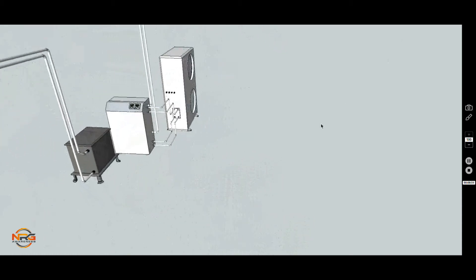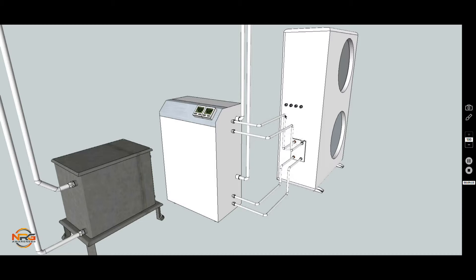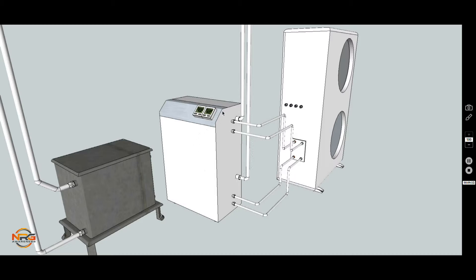If we look at what's happening with the heat pump, we have two parts. We have the outside, which is made up of two different heat collectors or heat pump apparatus, with refrigerant circuits coming from both of those, the top one and the lower one. This refrigerant would be pushed through the compressor, would increase the temperature of the refrigerant gas accordingly, and that high temperature refrigerant gas would be put through a plate exchanger within the unit. Likewise with the bottom one if it's operating, it'll pull the refrigerant gas, push it through the exchanger, so all of this high temperature hot gas will be passing here, and then the water will come down, cool the gas, strip away the heat, and deliver the heat back up and into the Energy Zone manifold.